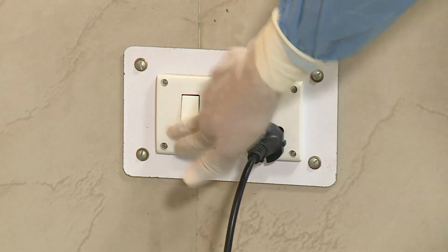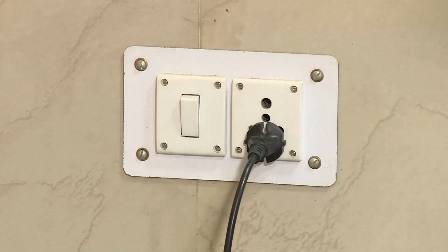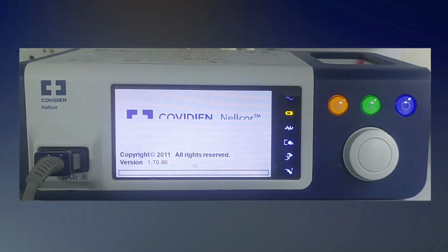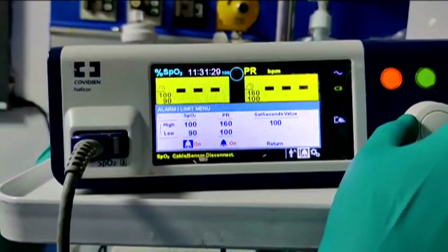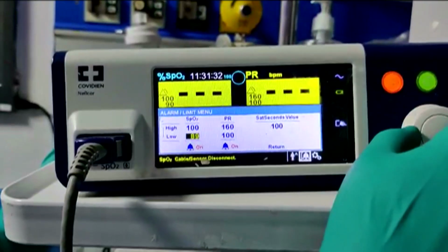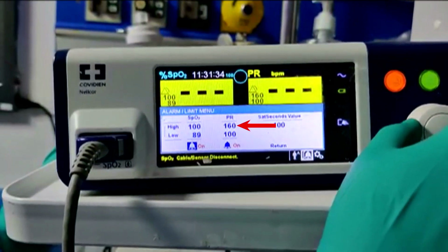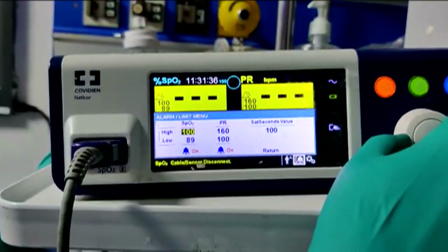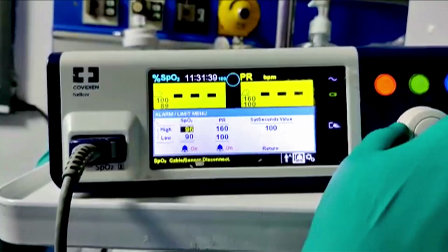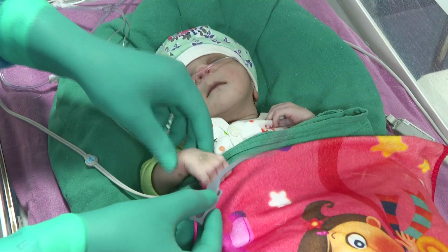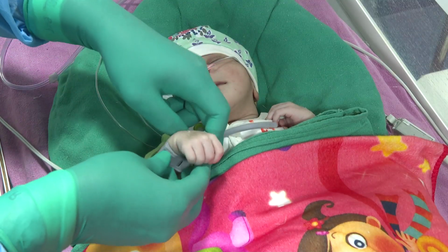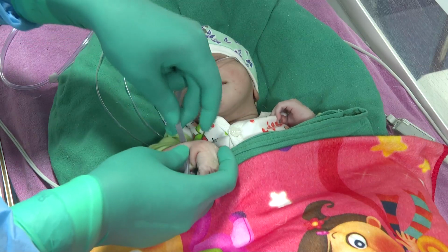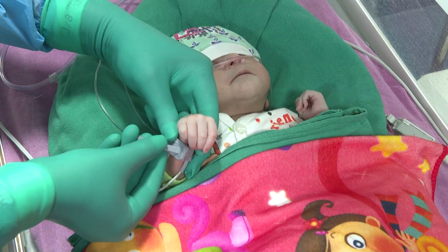First, connect the power cord switch to the main electrical supply. Switch on the machine by pressing the power button. Set the alarm limit for heart rate between 100 to 160 beats per minute and set the lower saturation alarm limit at 90 and the upper saturation alarm limit at 96%. Connect the patient sensor to the baby by wrapping it around the baby's hand or foot.